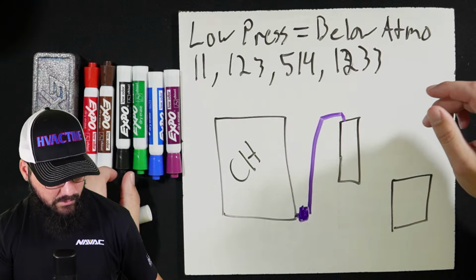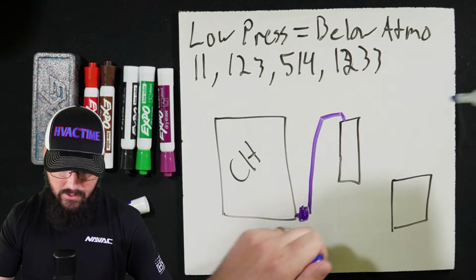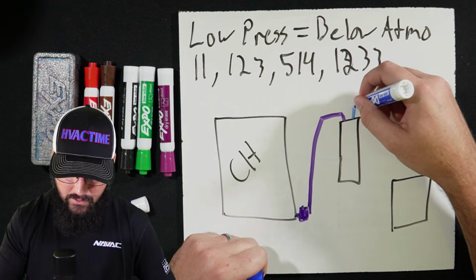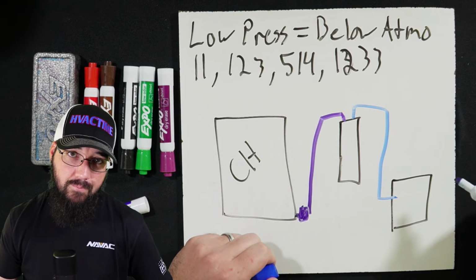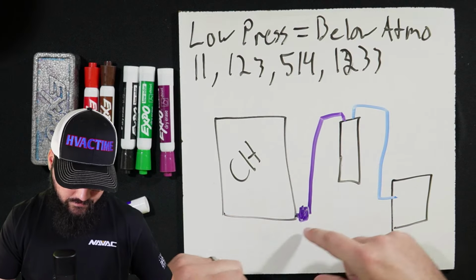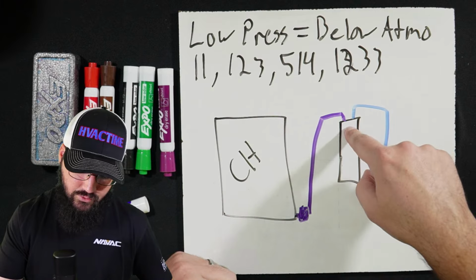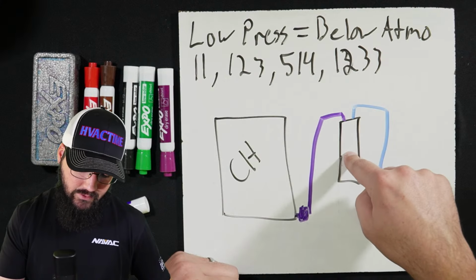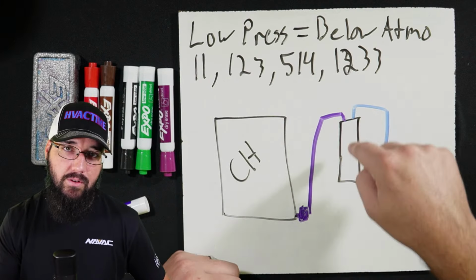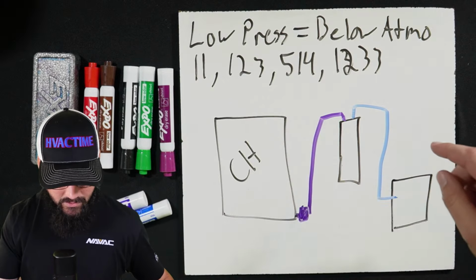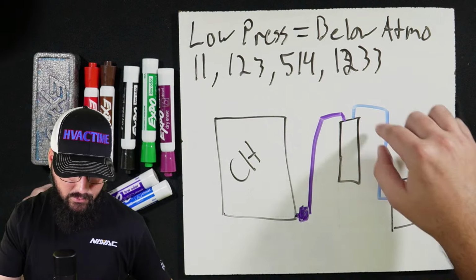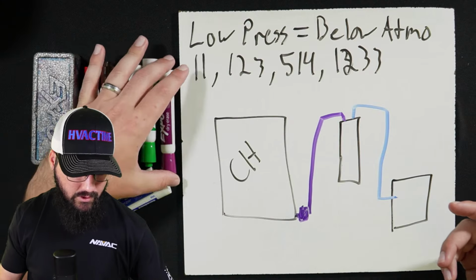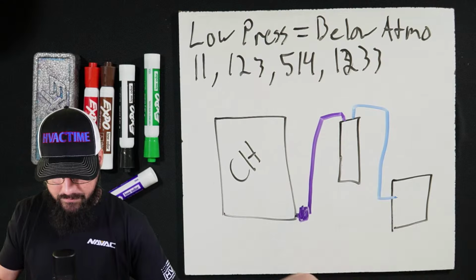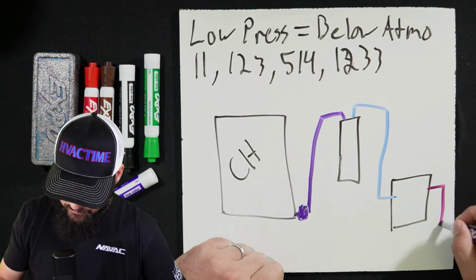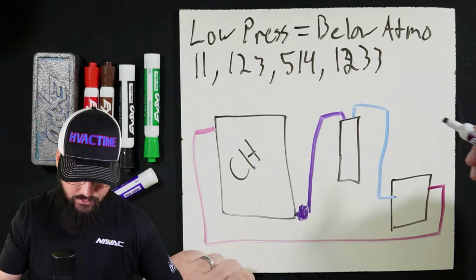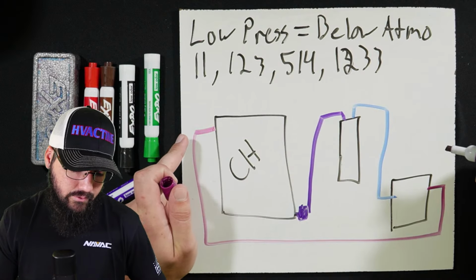Then we're going to be pulling vapor back off of this tank and into our recovery machine. So this process, what we're doing, this recovery machine is drawing pressure down on this tank. As this tank draws down, it naturally wants to siphon refrigerant back into the tank. Now, we have to send the vapor we're pulling off somewhere. It can't just sit in the recovery machine. So we're going to come out of the recovery machine and then back up into a vapor port.